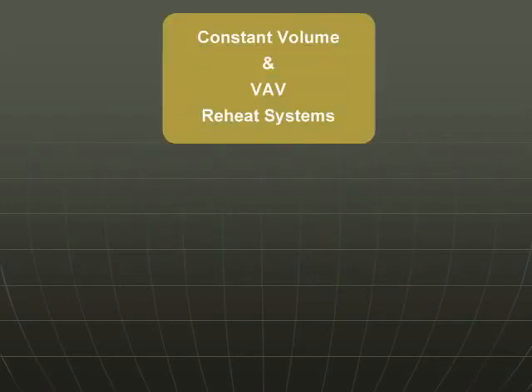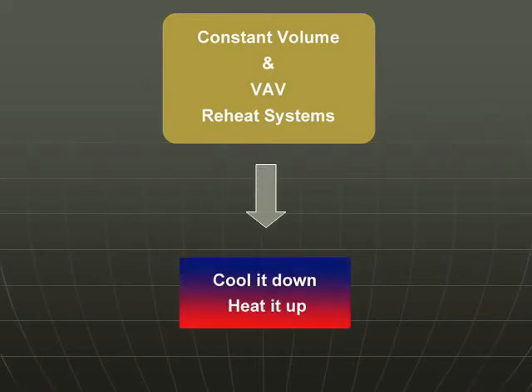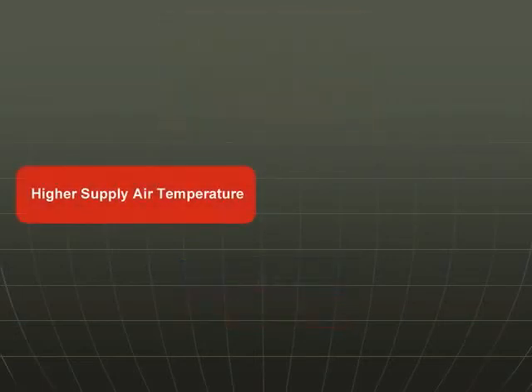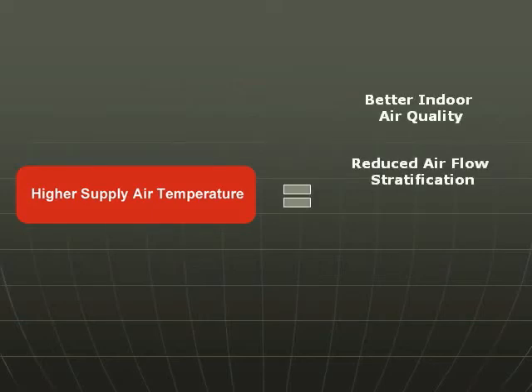With constant volume reheat and VAV reheat systems, maintaining the highest possible supply air temperature reduces the costly cool it down to heat it up energy wasting sequence. Maintaining the highest possible supply air temperature induces zone dampers to open, providing better indoor air quality and reduced airflow stratification within the conditioned space, as well as increased comfort and energy savings.